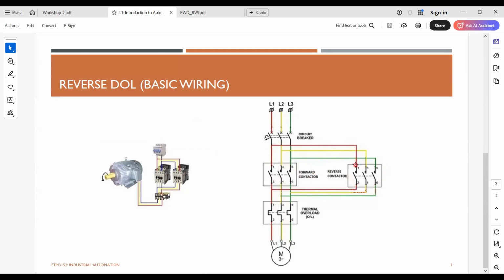It does not carry any additional features, for example, the interlocking, because you should never turn on the forward contactor and the reverse contactor at the same time, which will result in short circuiting two terminals of the lines, which results in large current going through. Sometimes it could damage your protection devices. Sometimes it could damage the motor as well. So there should be some interlocking. When the forward contactor is pressed, it should not allow the user to turn on the reverse contactor. For that, we can use either mechanical interlocks or electrical interlocks, or sometimes both are used.